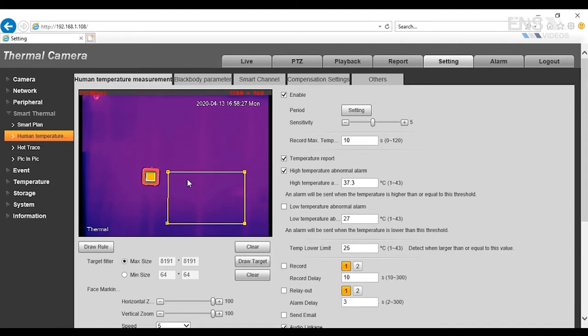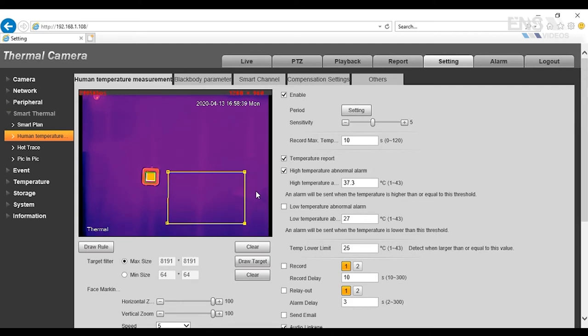Now, keep in mind that every person is a different height and also a different width. So what you want to do is when you drag the rectangle, you want to leave a little slack to accommodate for different sizes and shapes and heights of different people. Once that's done, you're going to check the temperature report, and then also High Temperature Abnormal Alarm because we're concerned about fevers. So by default in Celsius, you're going to set it to the 37.3 degrees Celsius.